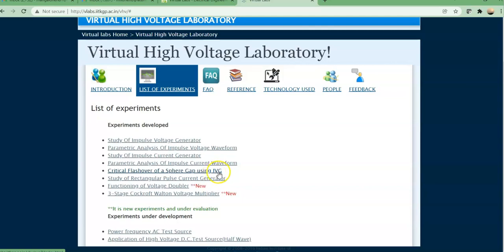IVG is impulse voltage generator, and this is critical flashover. We are not finding critical flashover here, we are just using this test setup, and the flashover voltage we get we will consider as the breakdown voltage of air.